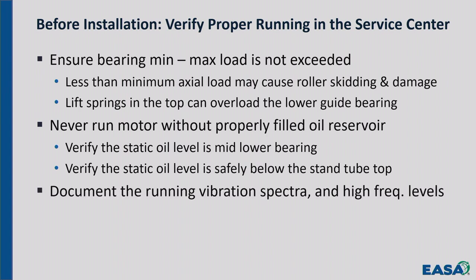When the machine's running in a service center, this is probably one of the most important things. You want to record the vibration. You want to take vibration spectra. Put your transducer on it and take a spectrum. On a machine, if it's horizontal, you take a horizontal reading, a vertical, and an axial. On a vertical machine, they're all horizontal. We usually refer to those as radial. Okay? So you might take radial in line with the junction box and radial at 90 degrees to the junction box.